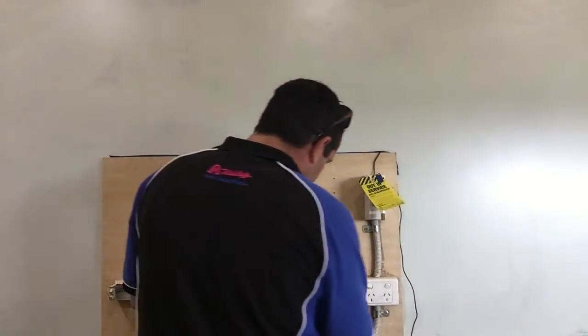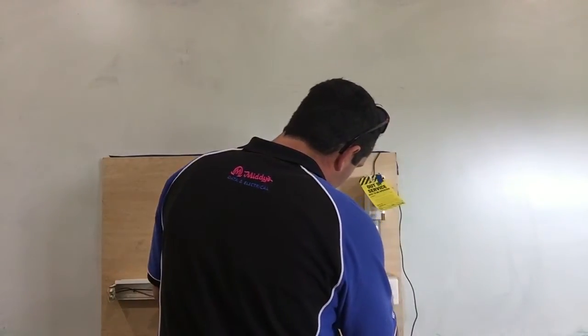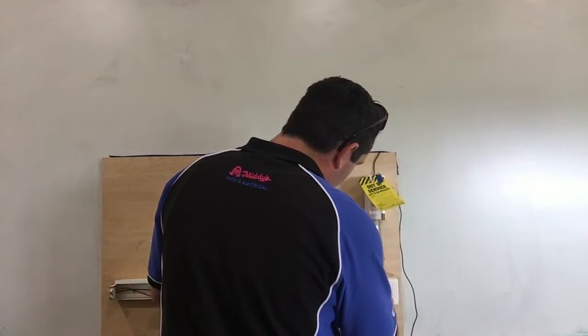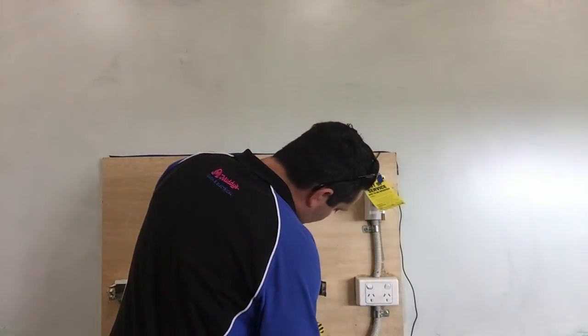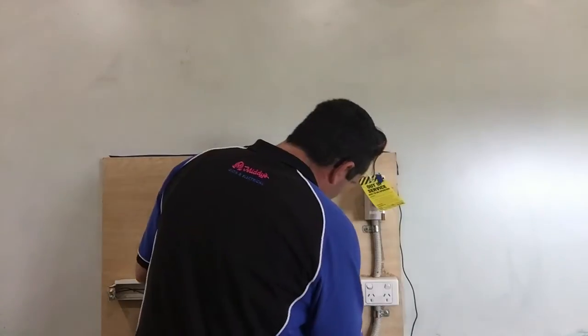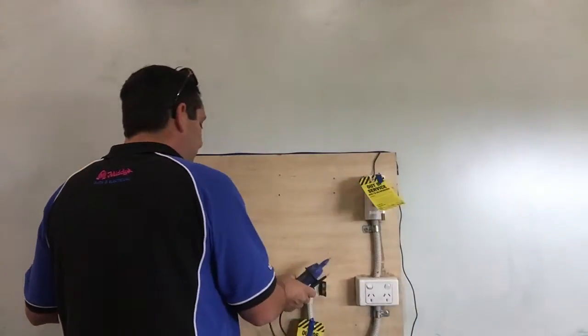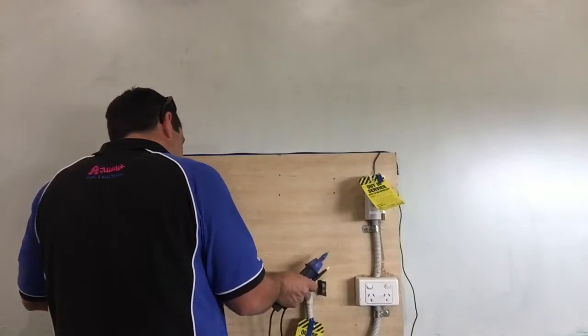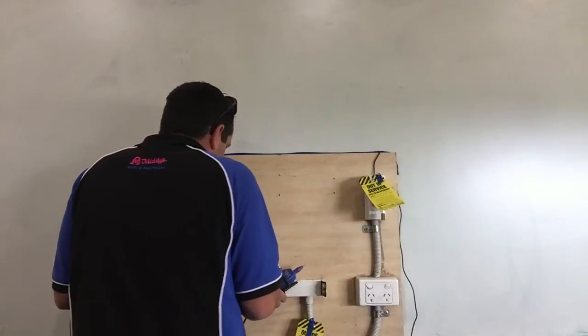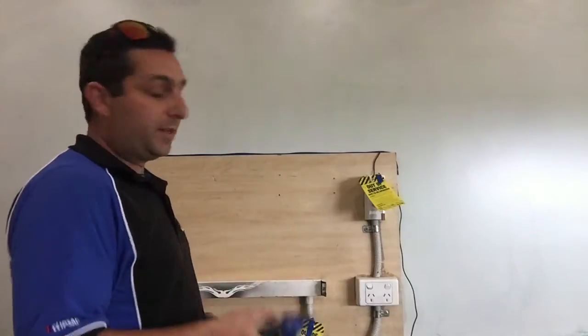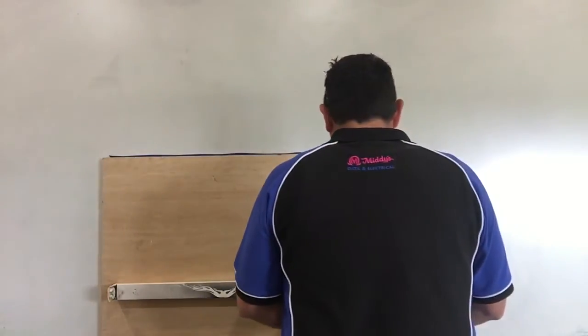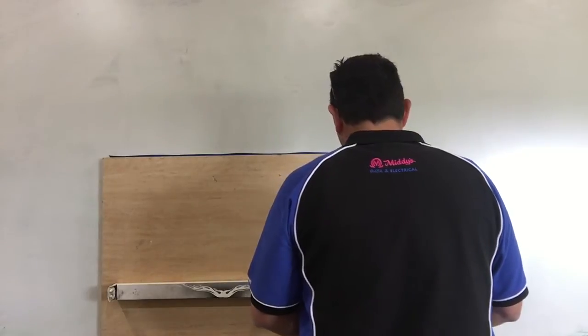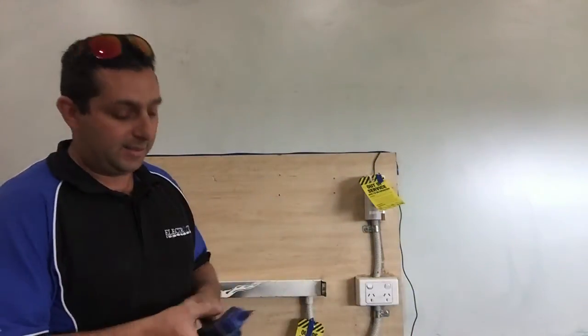Remove the cover from our earth point. Active, earth, neutral. Active, neutral, active, earth, neutral, earth. Again, this has come up as there being no voltage, but we can't take that as a given, because we need to retest our tester to make sure that something hasn't gone wrong with our tester in the meantime. Active, neutral, active, earth, neutral, earth. Now I'm happy to say that that is the circuit. This appliance is now isolated, and we can continue with the removal, the disconnection.